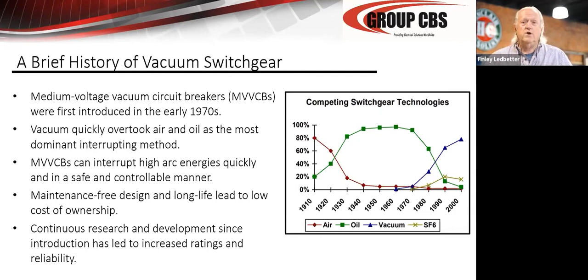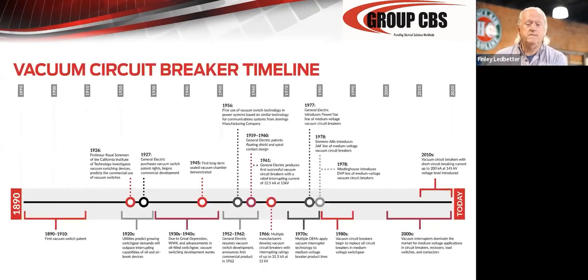An air breaker, you can go in and burnish the contacts, clean the contacts, and keep them in service forever. A vacuum breaker, eventually the vacuum interrupter will cease to do its job. There's been continuous research and development throughout their life, and consequently, you've seen a great improvement, and the vacuum breaker is a very stable piece of equipment. Now, there is no replacement on the design board right now that's close enough to speak about. So these breakers are with us for the immediate future.